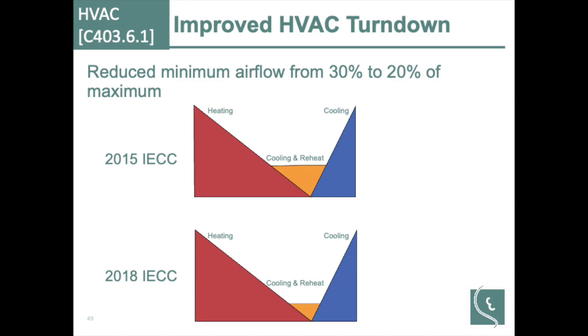I have a question about that. Yes. So generally, my understanding is the turn down of 30% is related to the minimum capacity of the VFD. And so how do you get a fan to slow down to 20% of its rated speed if the VFD only wants to go down to 30%? Yeah, this is dealing particularly with variable air volume systems. These tend to be larger systems. And so while any box may turn down to 20%, the system as a whole may not necessarily be operating down in this zone. This is a particular zone that may be.